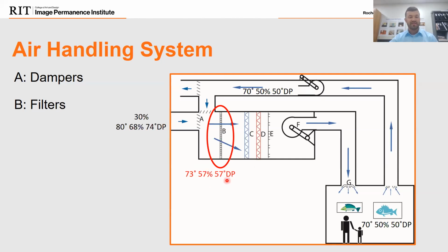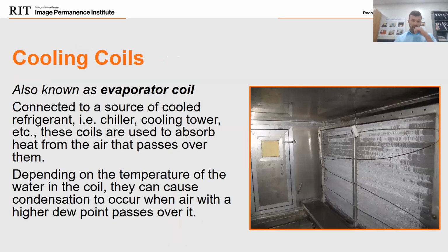Problem is we can't send this air downstream to our space. We need at least a 50-degree dew point, 70 degrees in the space, and 50% relative humidity. So our dew point's too high, relative humidity is too high, and our temperature's too high. So we have to find a way to bring that down and get that all back under control. The main component we're going to use to achieve this is our cooling coil. The cooling coil can also be known as the evaporator coil, connected to some source of cooled refrigerant, whether it's chilled, whether it's a chiller, a cooling tower. These coils are going to be used to absorb heat.